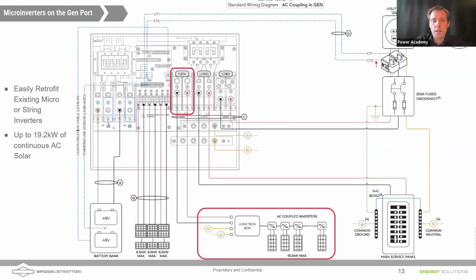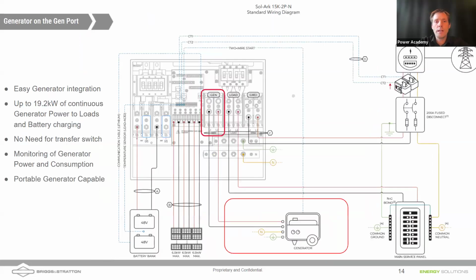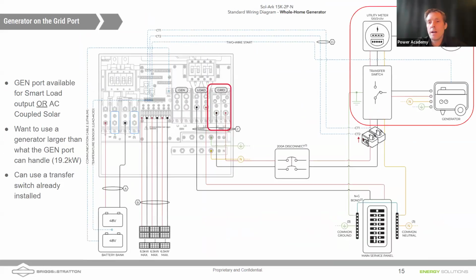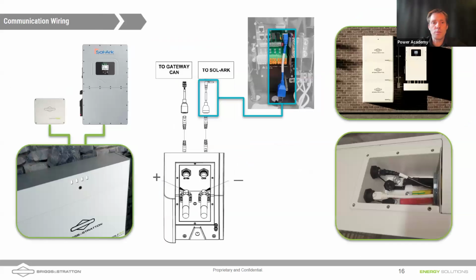So just to familiarize ourselves as we go through, we're showing an example here where we have AC coupled solar coming in through the gen port. So that's one wiring example that we're going to be talking about how to program for. Here's an example where we're bringing a generator in through that gen port. So that generator port is limited to 19 kilowatts of continuous power, that's 80 amps. Here's an example in which we've got a generator or the grid coming in on the utility port for the inverter. In this case, we could have a generator bigger than 19 kilowatts, bigger than 80 amps of continuous power. So if we're using our 26K, you could get that full 112 amps. It's still going to be controlled by two-wire start, and you'll still only start up that generator once the batteries get low, as long as you program it correctly. And one of the advantages of this setup is you leave that generator port open, perhaps for AC coupled solar, or perhaps for a smart panel, which is what I like to use it for.